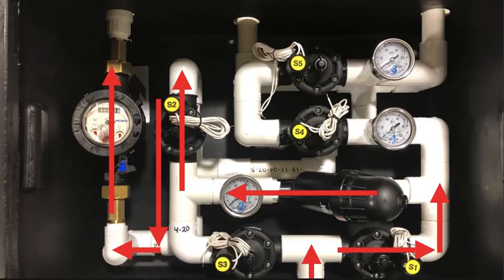If we go back to the slide just previous to this, you see this disk filter right here. This is collecting and catching organics as the dose is going on, but multiple times a day, it's going to reverse the flow and actually flush out everything that this has been collecting and send it back through that vent line back to the very beginning of the system.